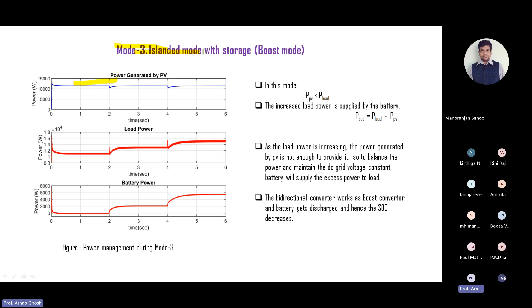In this mode you can see it's islanded mode, boost mode. So PPV is less than P load, meaning the PV generation power is less than your load power. So P battery equals P load minus PPV, so additional power is coming from the battery.